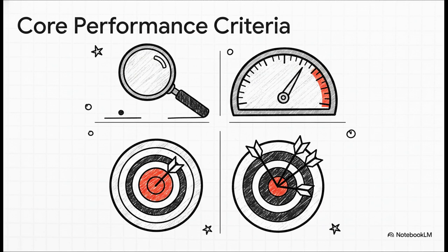If your resolution is too high, it might pick up minute, unwanted fluctuations or background noise that's going to require complex additional processing to filter out. We also want high sensitivity, which is the output change per input change. But higher sensitivity almost always means higher cost.